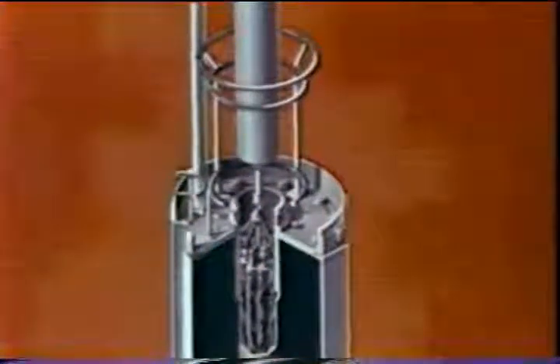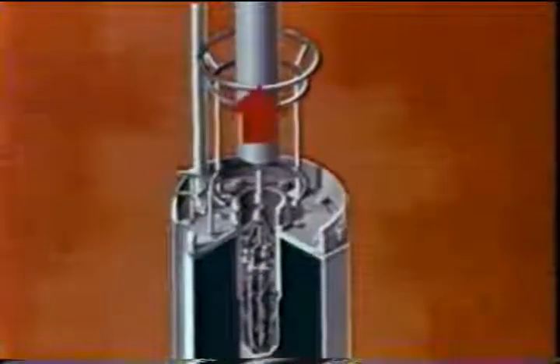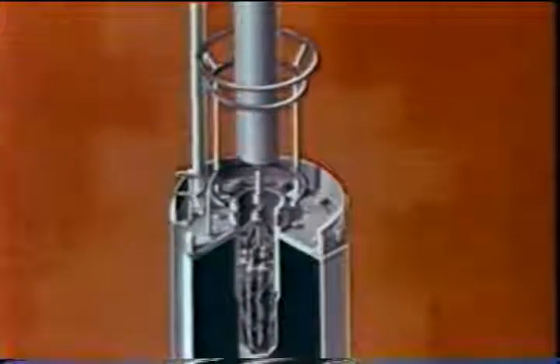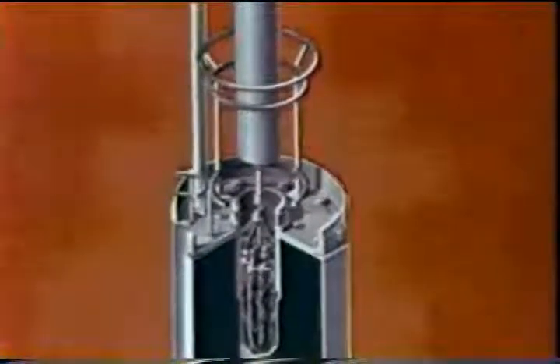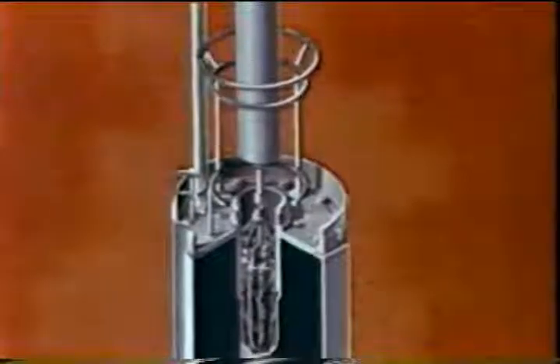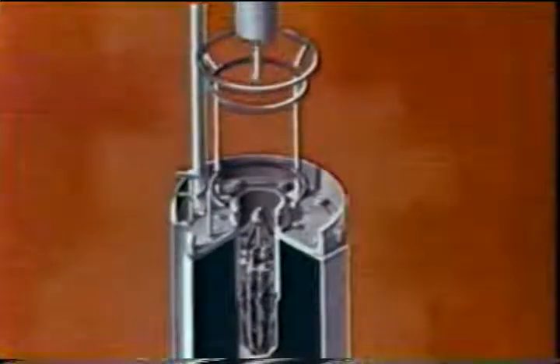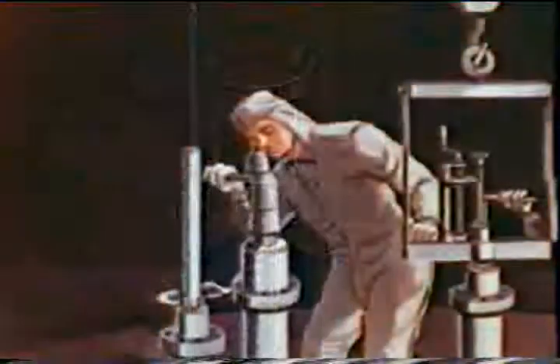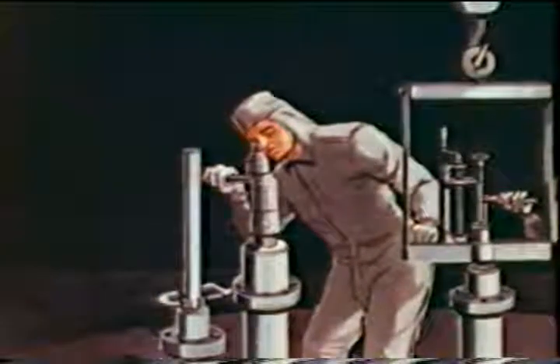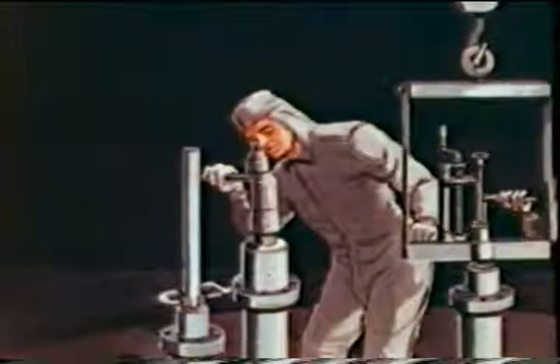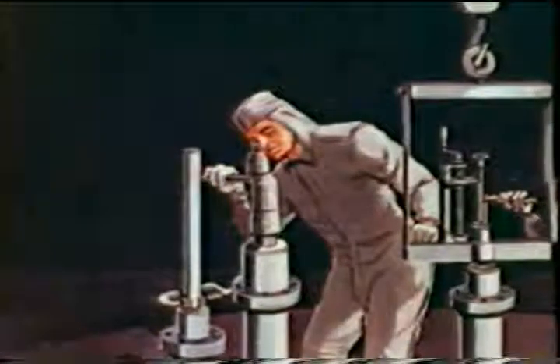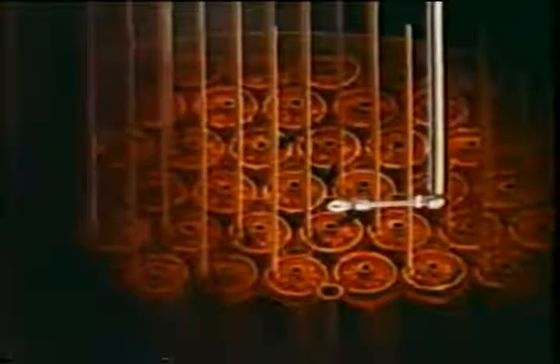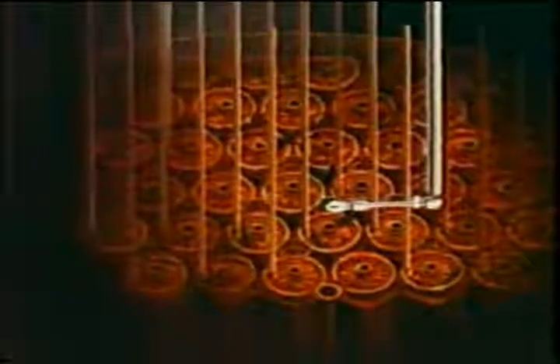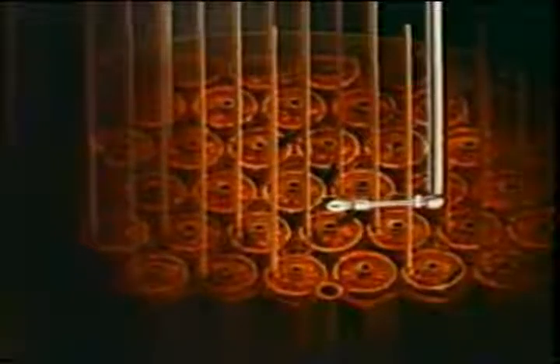The two remaining damaged fuel elements neither broke nor could be raised by the usual fuel removal process. To facilitate recovery work, the two hanger rods were snapped loose. Before recovery work could be commenced, it was necessary to determine the condition of the core. This meant the development of scopes, lights, probes, and tools which could operate in the highly radioactive core where the temperature was maintained above 300 degrees Fahrenheit.